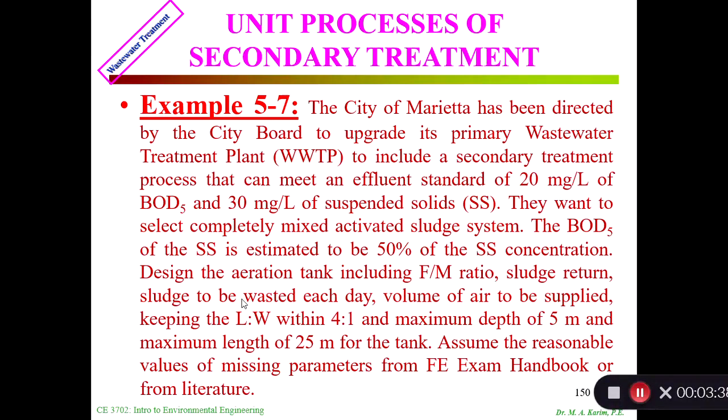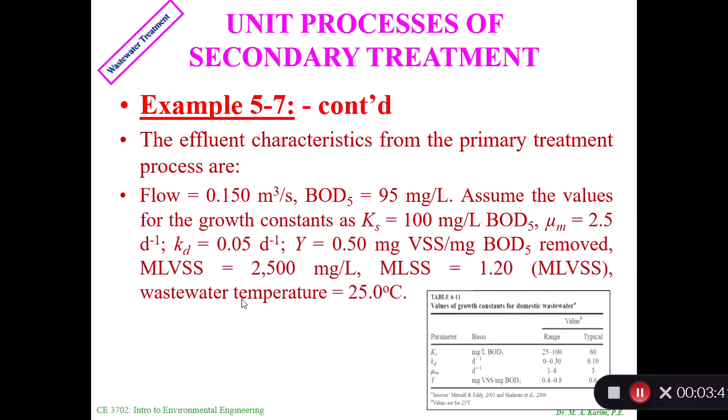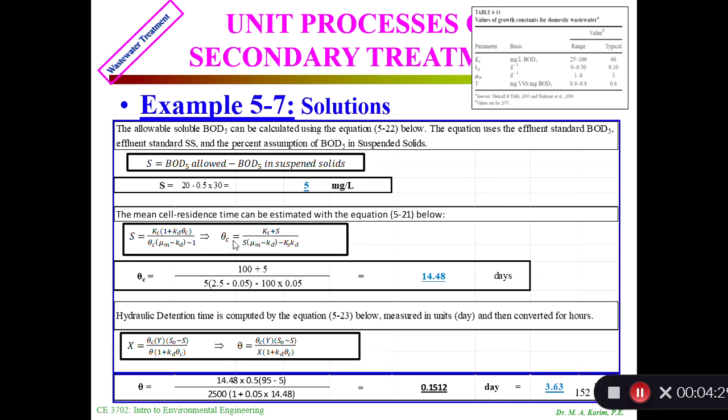The influent characteristics: flow is 0.15, BOD5 is 95. Assume values of growth rate Ks = 100, μm = 2.5, Kd equals this, Y = 0.5, and MLVSS is 2500 mg/L. MLSS is 1.2 times MLVSS. Wastewater temperature is 25°C. We need to know the temperature because we may need to convert something based on temperature. This is the table I showed before where we used to get those values.